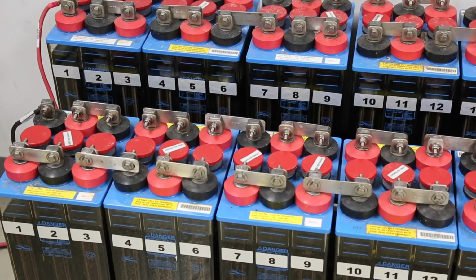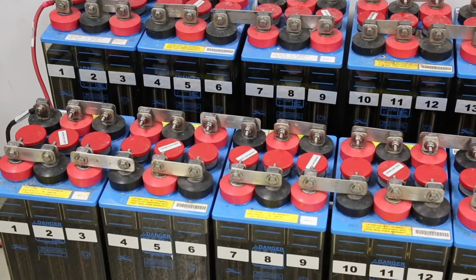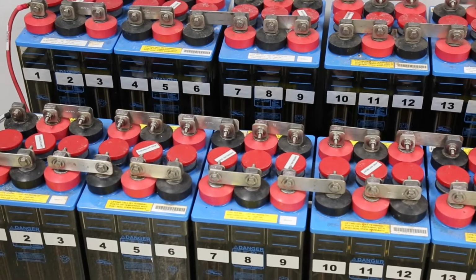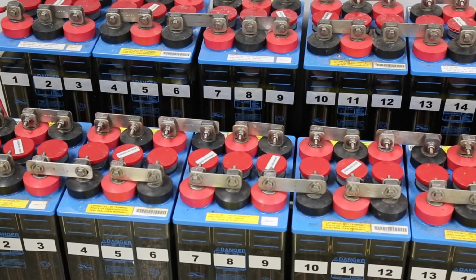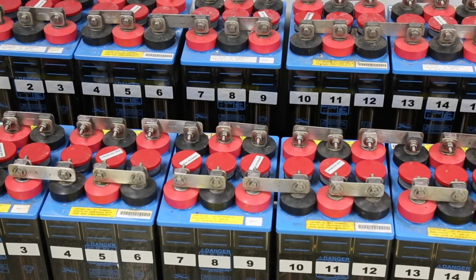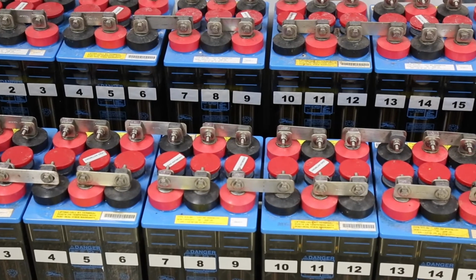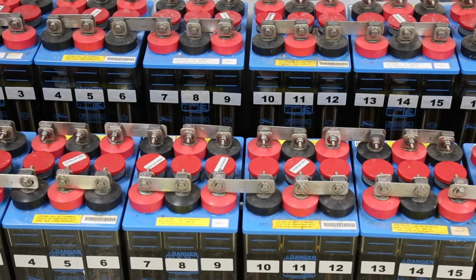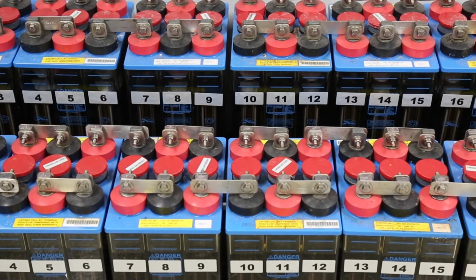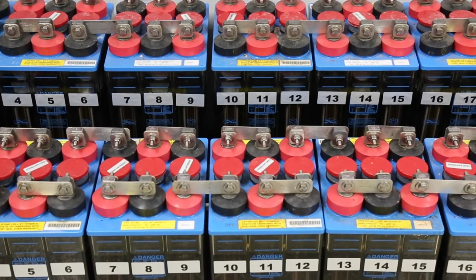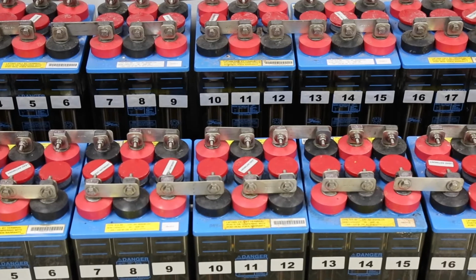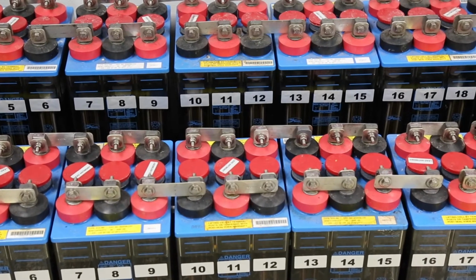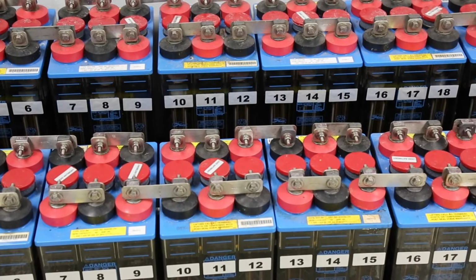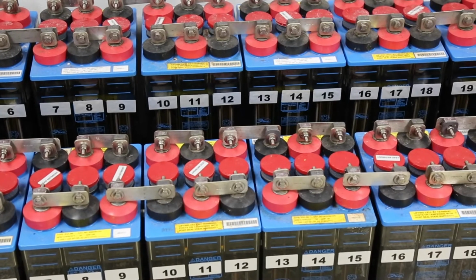As the plate size increases, the internal impedance of the battery drops. Large flooded batteries can have very low impedance values. In order to test these batteries, you must use a test set that tests with high current. So let's think about this for a minute. When trying to measure a low resistance value, do you use a multimeter or a low resistance ohm meter?